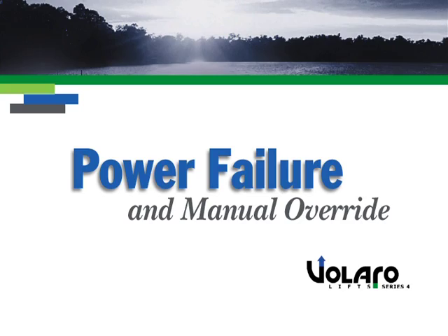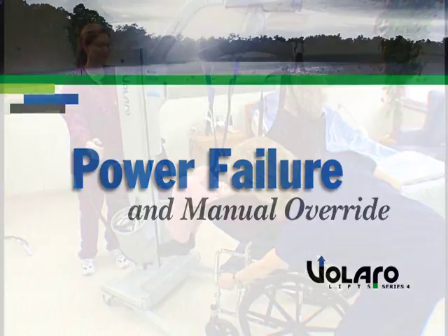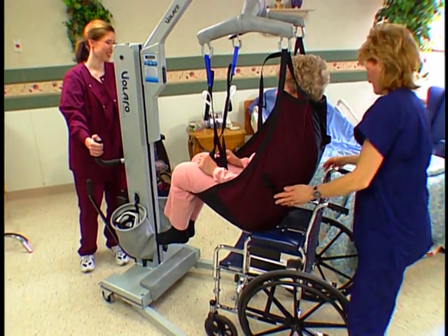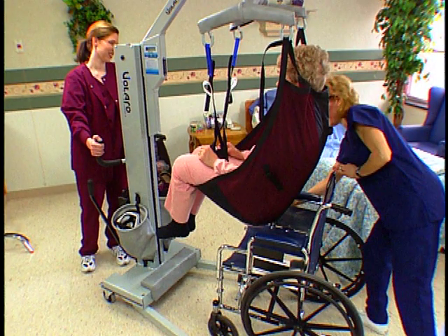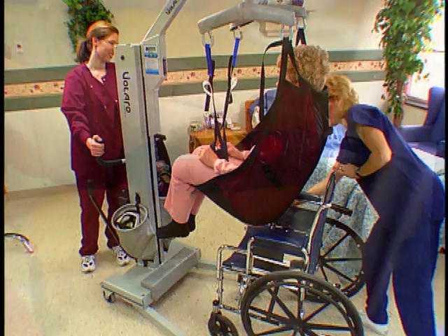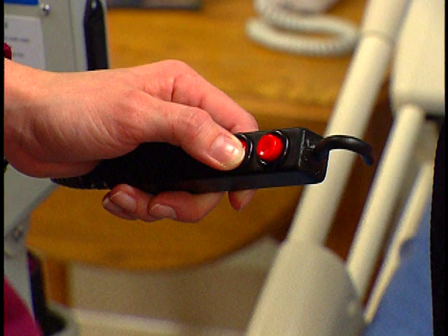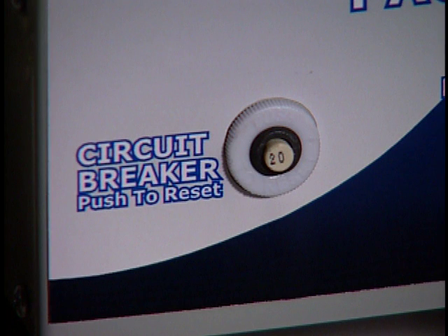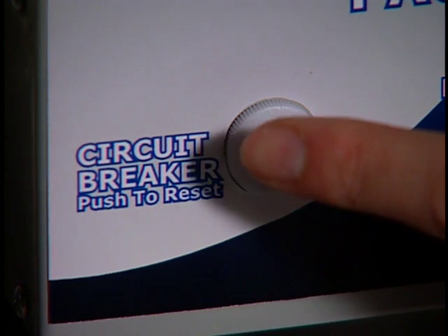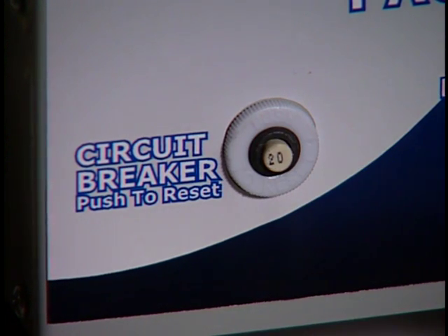Series 4 Power Failure and Manual Override. If for any reason your Series 4 lift should stop in the middle of a transfer, don't be alarmed. The person in the lift is perfectly safe. The first thing to do is check if another control switch will operate the lift. If this is unsuccessful, check the circuit breaker on the front of the battery receptacle. If the breaker has popped out, simply press the button and attempt to lift.